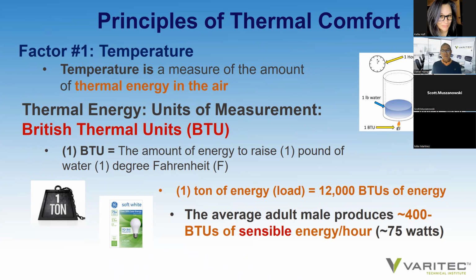Thermal energy is also measured in units. The standard for units of measurement are British thermal units, otherwise known as BTUs. One BTU equals the amount of energy to raise 1 pound of water 1 degree Fahrenheit. That's simple. 1 ton of energy, because we often hear HVAC loads in the form of tonnage, 1 ton of energy is equal to 12,000 BTUs of energy. And this is really in relation to standard conditions. In other words, 95 degrees at sea level on your ambient condition, so 12,000 BTUs of energy.